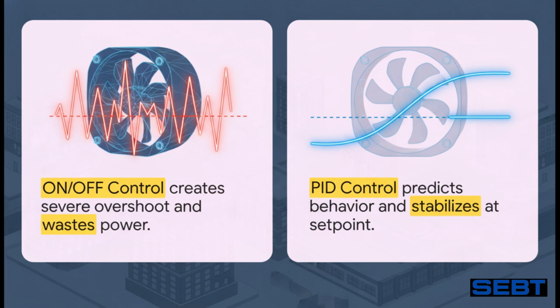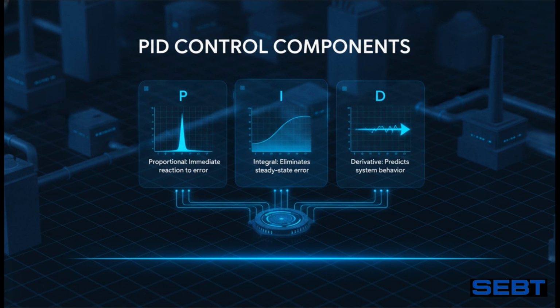We have PID control. This is smart. It actually predicts system behavior. It gradually adjusts those VFDs and valve positions, gently guiding the temperature until it stabilizes perfectly. And I mean precisely at our set point. All right, let's actually break down the math behind this PID logic.